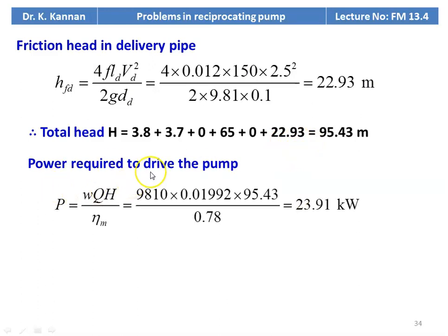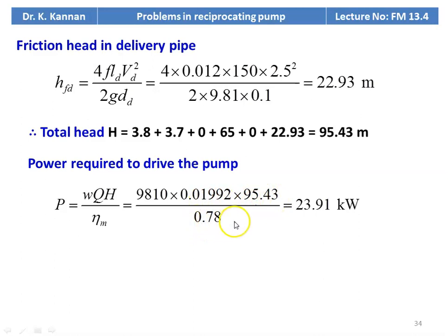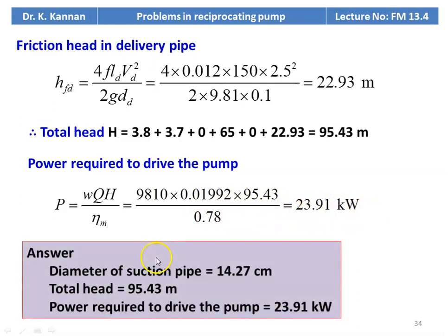Power required to drive the pump: P = W × Q × H / η_m = 9810 × 0.01992 × 95.43 / 0.78 = 23.91 kilowatt. The answers: diameter of suction pipe = 14.27 centimeter, total head = 95.43 meter, power required to drive the pump = 23.91 kilowatt.